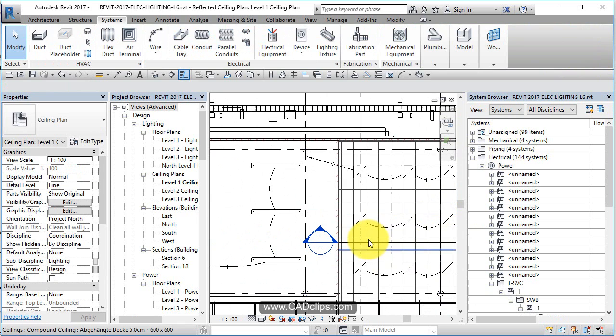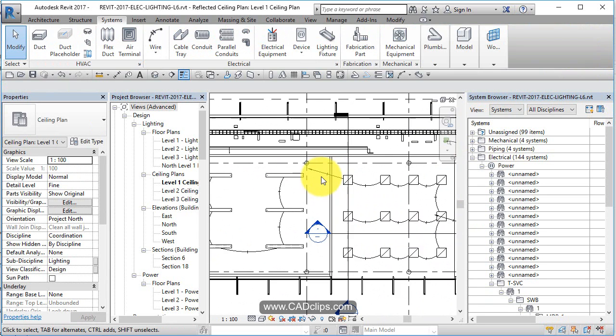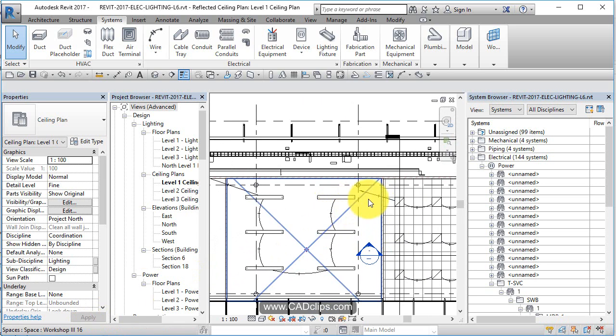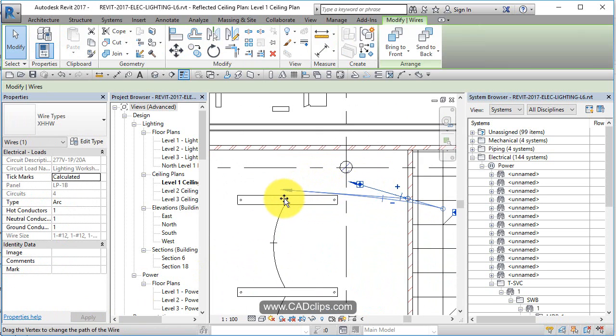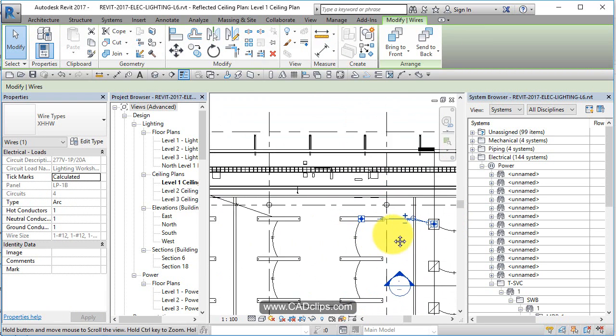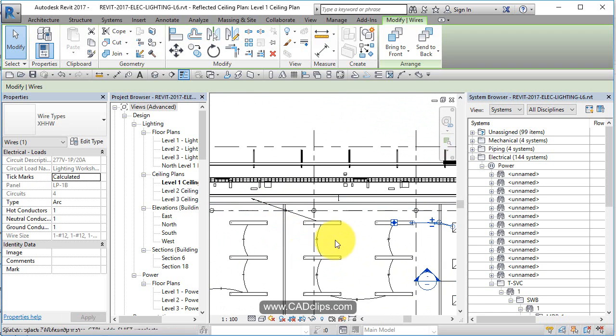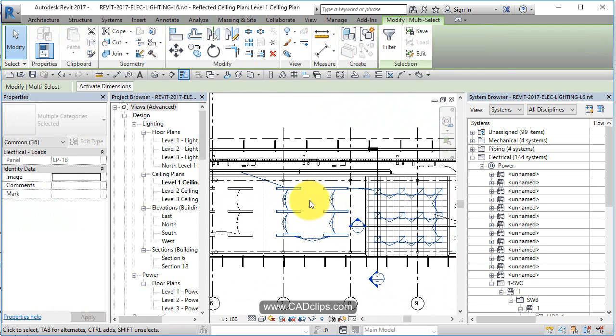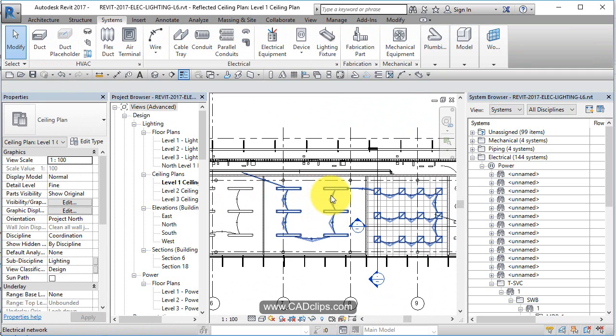If you add more than one circuit into a network — hover over an element and tab — you'll see it's labeled as a network down here, as opposed to a circuit. If you take one set of wires and connect it to another, the home run gets a double arrowhead because it now has two circuits on it. Hover and tab to see the difference: a network ties multiple circuits together — don't get them mixed up.